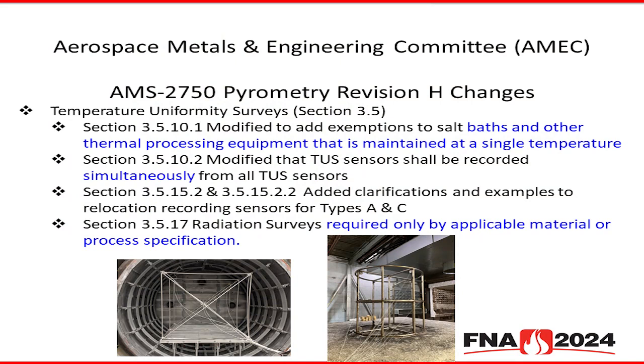We modified the TUS requirement so all recorded sensors have to be recorded simultaneously. Someone found out there was a guy out there doing his TUSs by handwriting the numbers in. They couldn't really write an NCR on that, but we clarified it so you need some sort of recording system to capture your TUS data, versus just handwriting it in - that's why we used the word simultaneously for all those readings.